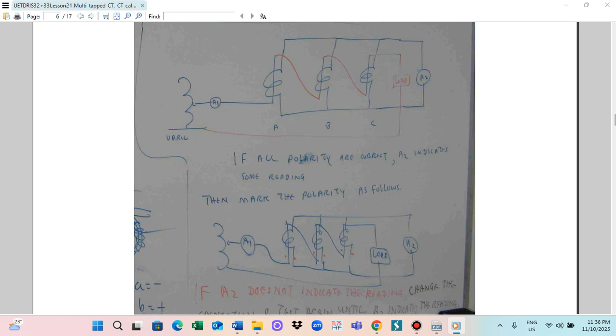Resistance is the amount of resistance that can be connected to the CT secondary. So in this case, the CT connection is very important. If you connect the CT to the circuit path, the secondary is usually connected to a relay and measuring instrument, so they should have the appropriate resistance. So this burden resistance can be calculated by this equation: reference voltage divided by 20 times rated secondary current. So this equation. Another one is the CT ratio error.